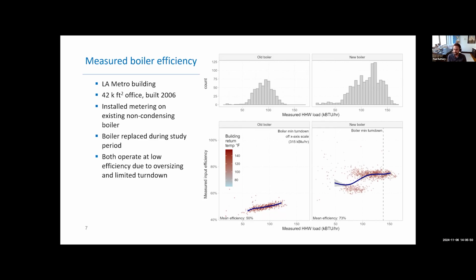This is the brand new high turn down condensing boiler, but still quite oversized. This unit has a nominal efficiency of about 90%. And even with this brand new piece of equipment, the measured efficiency is only about 73%, again because of an oversizing issue. So these sorts of results highlight that there's quite a bit more efficiency improvement we can get by focusing in on the plant and appropriately sizing that. And that's generally not being captured by engineering practice today. It's really not a core focus area because boiler capacity is cheap. So the driver for this really has to come from the facility owner or somebody else on the team to say, no, we don't want a giant boiler. We'd rather have an appropriately sized boiler and take some tiny measure of risk that on the coldest day of the year, it'll be a degree or two cold, so that we get that increase in efficiency.